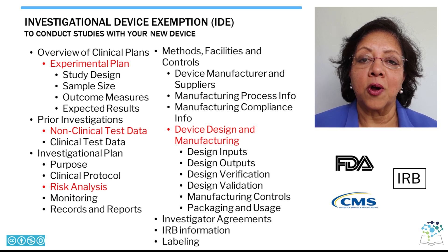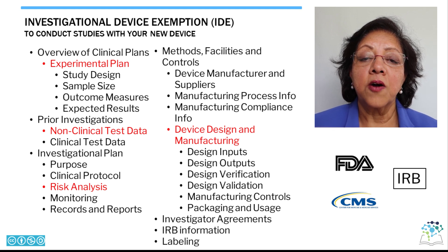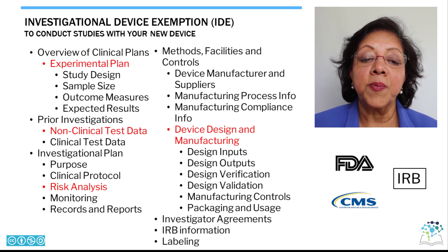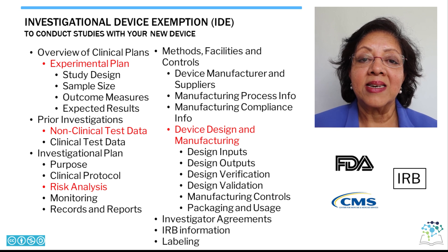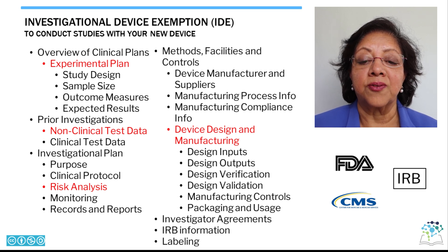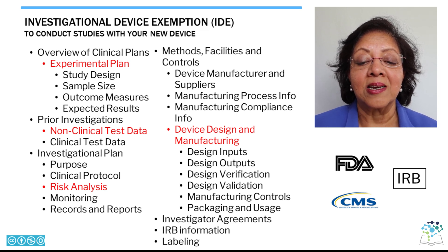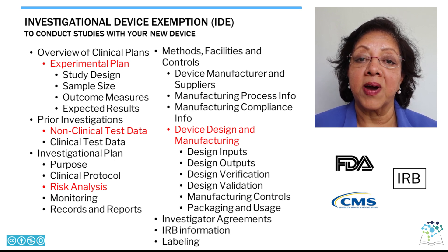Appropriate facilities that follow good laboratory practices and good manufacturing practices must be utilized. While reviewing your IDE application, the FDA will also evaluate your clinical protocol and the primary and secondary outcomes. IRB approval will be required for the clinical protocol and informed consent documents that include risk and benefit information. Independent external research and clinical monitoring may be required. You will also have to take into consideration several ancillary issues such as insurance and indemnification of OEMs and clinical partners. These can be very challenging for a small company and require considerable financial reserves.